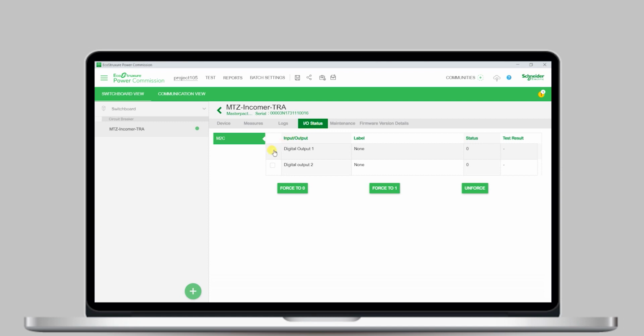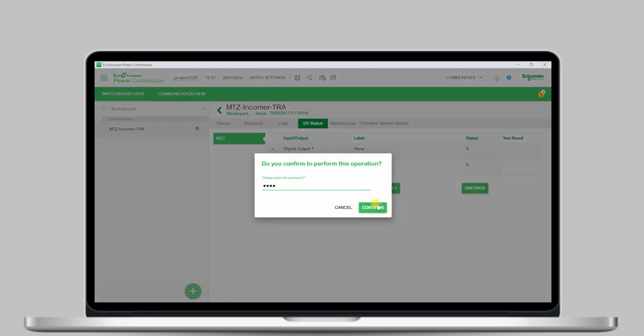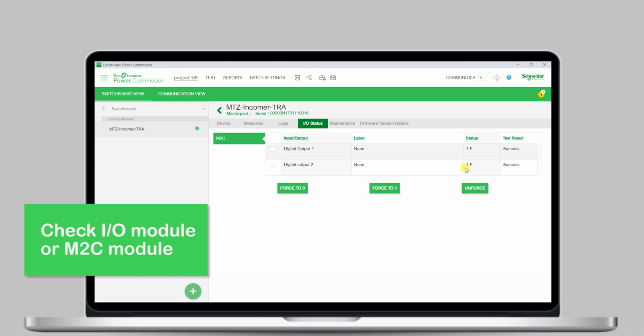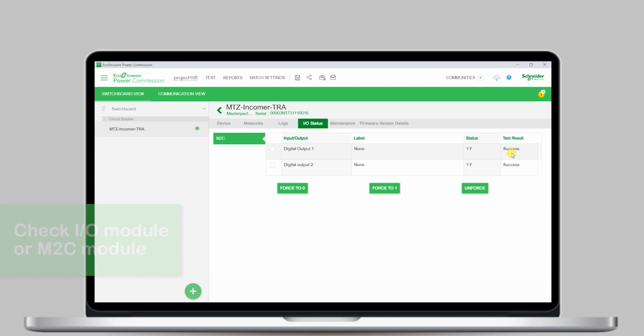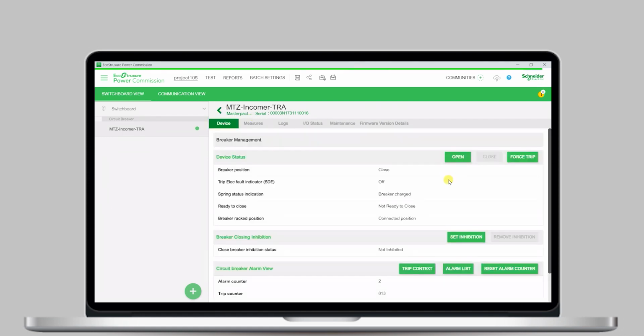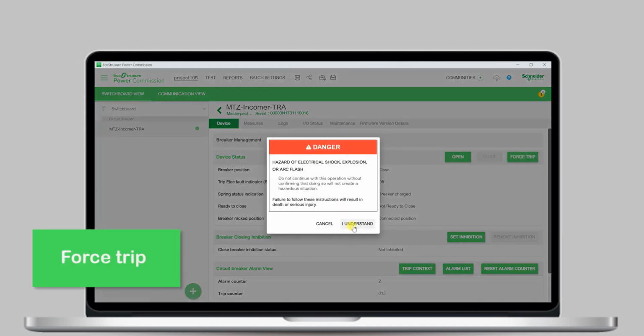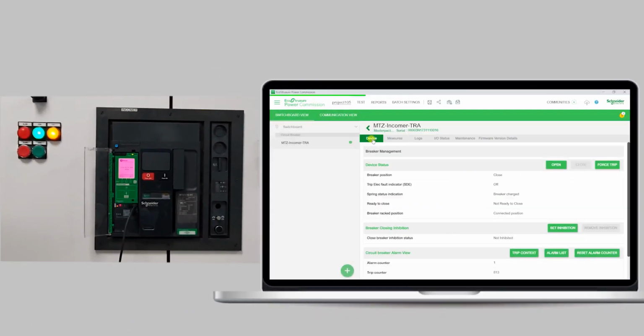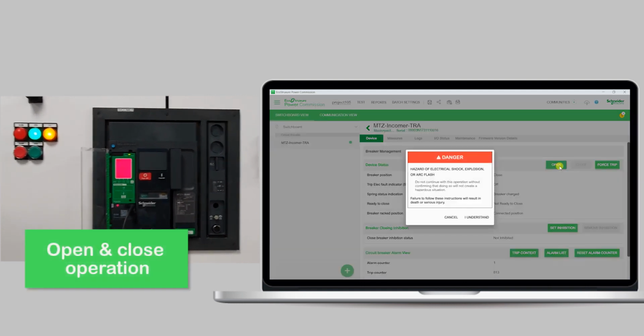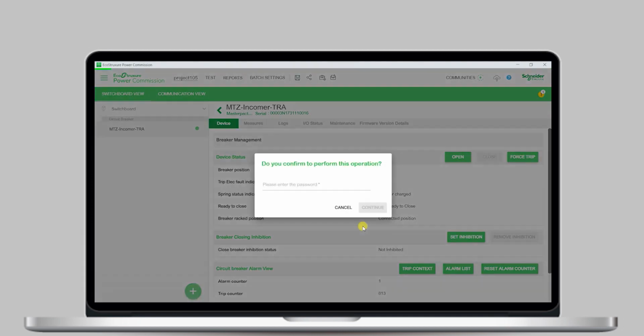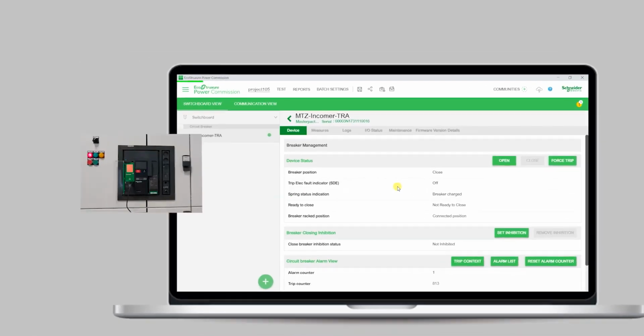If your circuit breaker is wired with Enerlin'X I/O module or M2C module, use the Device Checkup I/O tab to see the status of digital input and validate the wiring is done properly. You can also trigger the outputs to check if the connected relay or device gets activated. In the Device Checkup feature, you can also test if the circuit breaker trips by using the force trip function. If the breaker is installed with optional accessories of MX and XF coils, you can also test the open and close operation of the breaker. All these test results will appear in the EPC project report.